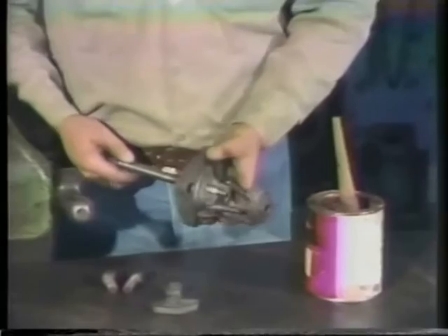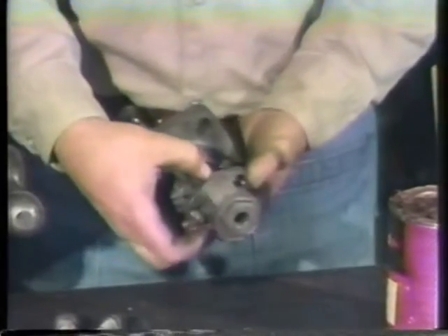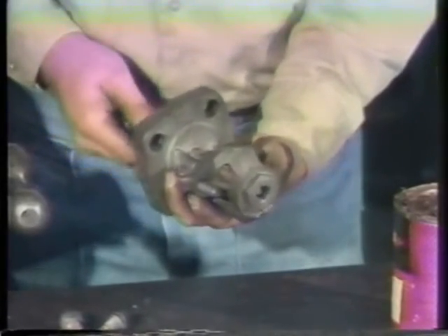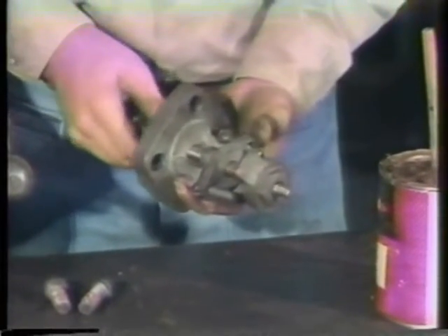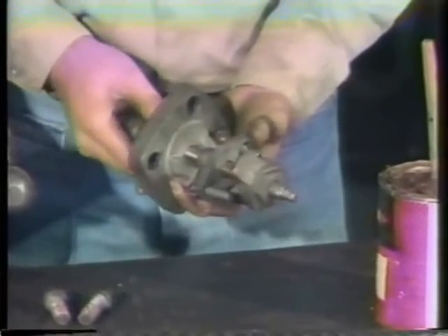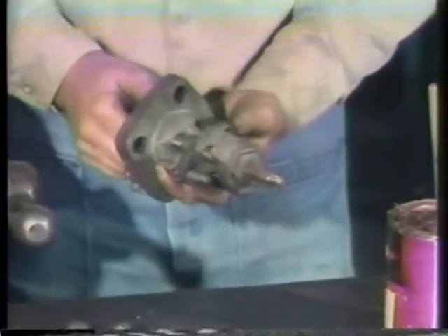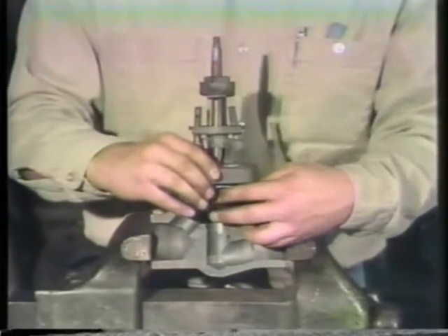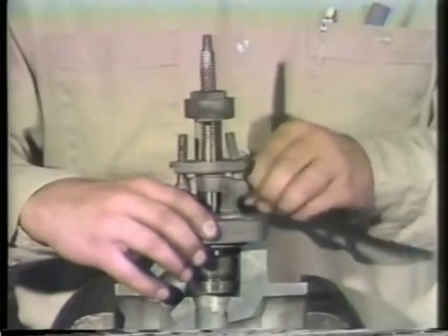Keep in mind what the valve will be used for. Once these parts are lubricated, put the stem through the bonnet and slide the two-part packing gland over the stem. Then carefully thread the stem through the yoke bushing. Continue turning until the valve is near the full open position. Now we can put this assembly back on the valve body. First, set in the Flexitallic gasket. Always use a new Flexitallic gasket. Never reuse one which has been previously compressed — it will not seal properly.